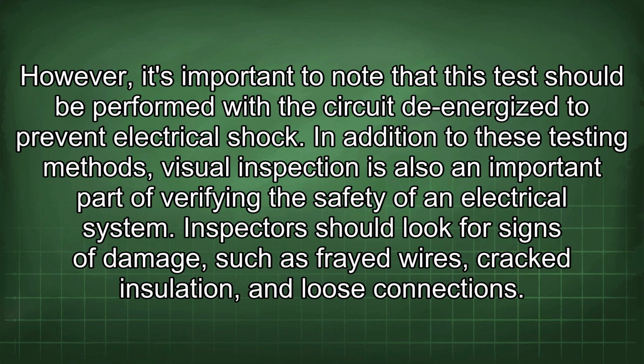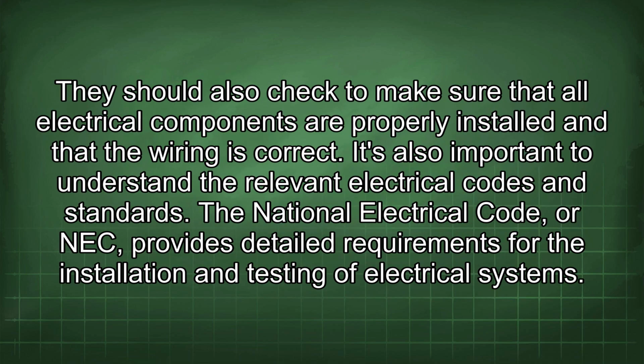In addition to these testing methods, visual inspection is also an important part of verifying the safety of an electrical system. Inspectors should look for signs of damage such as frayed wires, cracked insulation, and loose connections. They should also check to make sure that all electrical components are properly installed and that the wiring is correct.